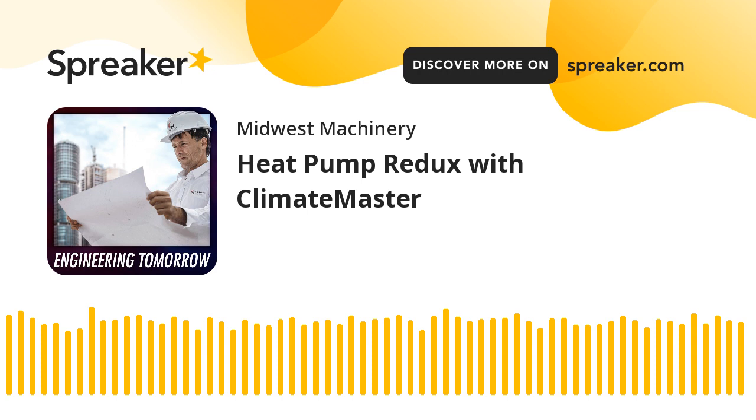That's significant, Dan. That's a big payday right there. No, it certainly is. So when you're looking at options and funding, or it's out of budget, this is one option. With variable or water source heat pumps, we do have options. We have a typical 2-pipe system. Well, it's a little over budget. Let's try a single pipe application. With a single pipe application, you're reducing your materials probably about 25 to 35%, and you're also going to reduce the amount of labor that you're doing on the install.